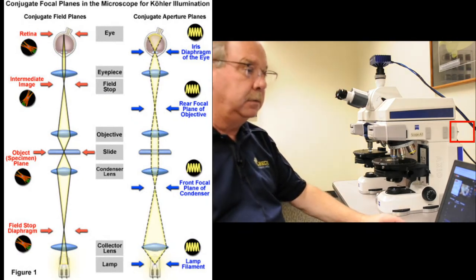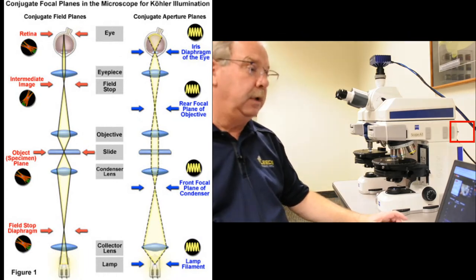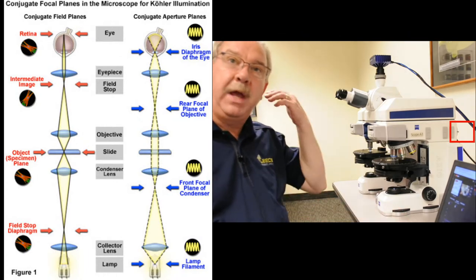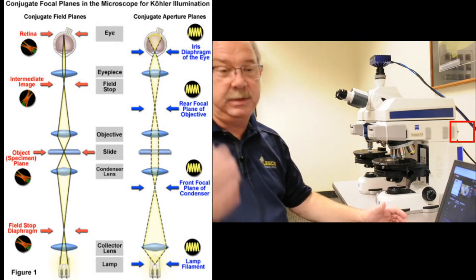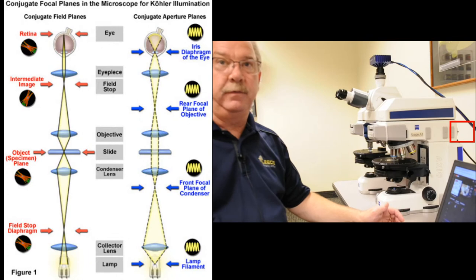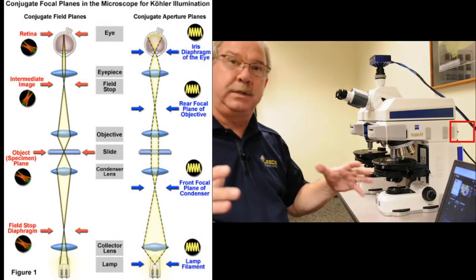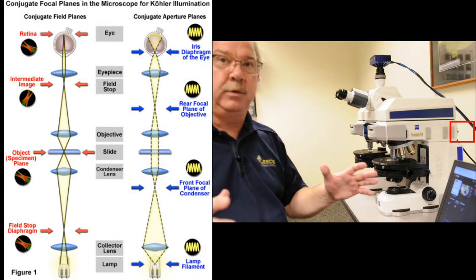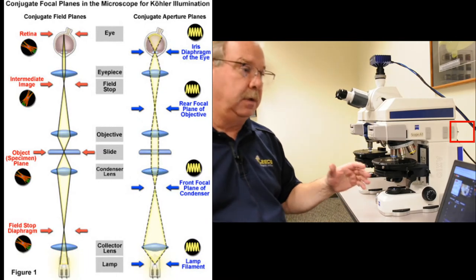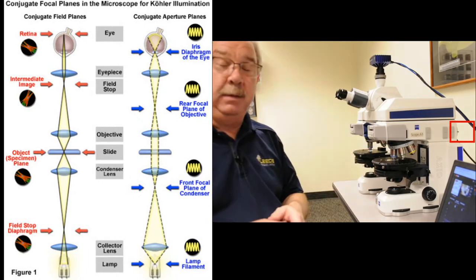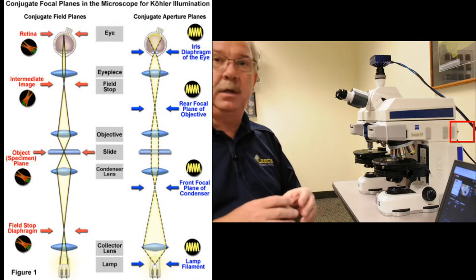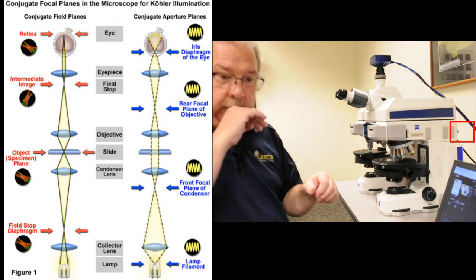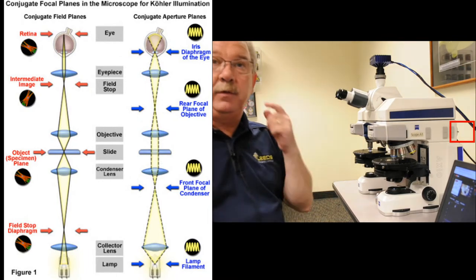You could actually measure the diameter of that reduced-diameter diaphragm, and it would correspond to the field of view of the eyepiece. In this case, we have a 23 millimeter field of view — the largest of any comparison microscope out there — and we could go in and measure that diaphragm and find it to be 23 millimeters in diameter. The final conjugate field plane is in the back of your eye, in the retina. I see the sample in focus, I see a nice sharp edge around my image, and if I were to close down the field diaphragm, I would see it in focus as well.